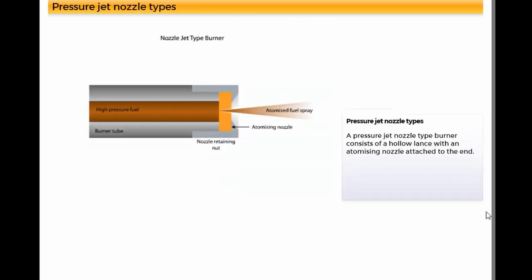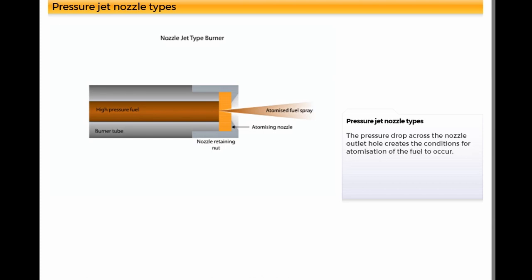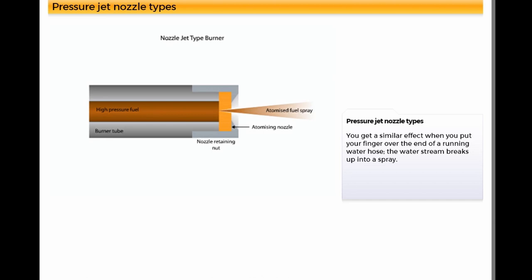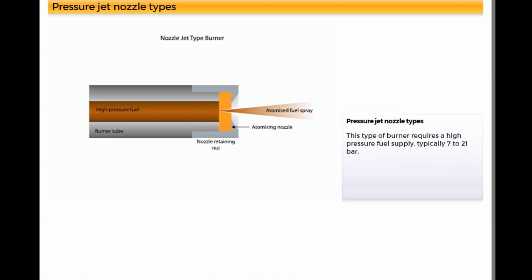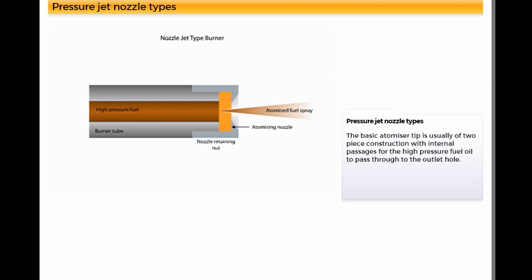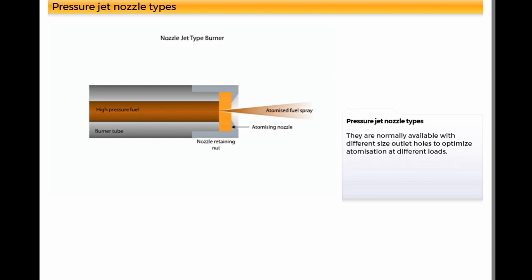A pressure jet nozzle type burner consists of a hollow lance with an atomizing nozzle attached to the end. The pressure drop across the nozzle outlet hole creates the conditions for atomization of the fuel to occur. You get a similar effect when you put your finger over the end of a running water hose. The water stream breaks up into a spray. This type of burner requires a high-pressure fuel supply, typically 7 to 21 bar. The basic atomizer tip is usually of two-piece construction with internal passages for the high-pressure fuel oil to pass through to the outlet hole. They are normally available with different size outlet holes to optimize atomization at different loads.